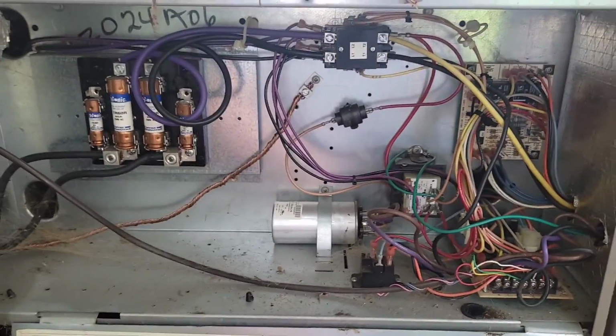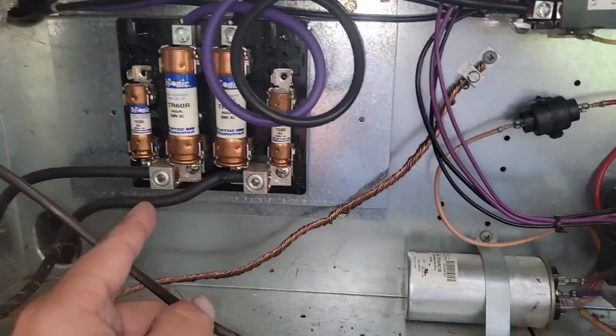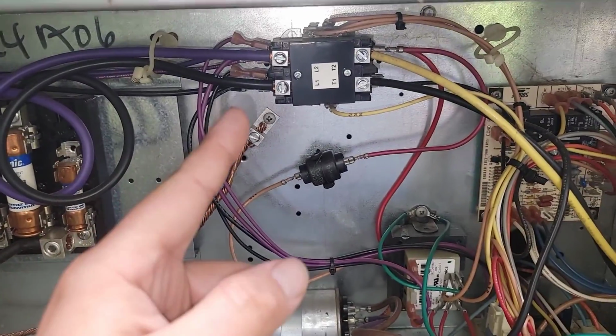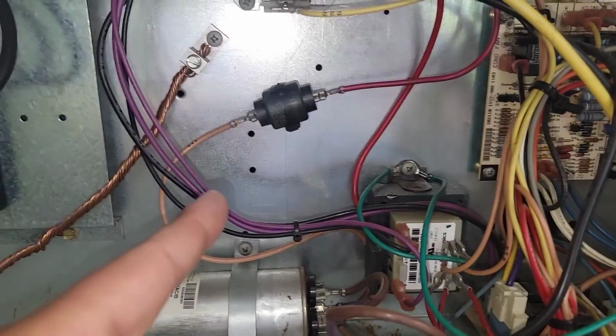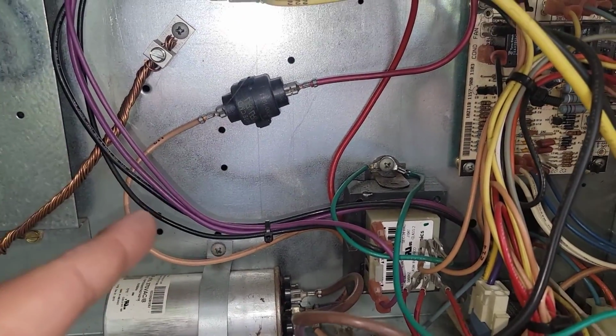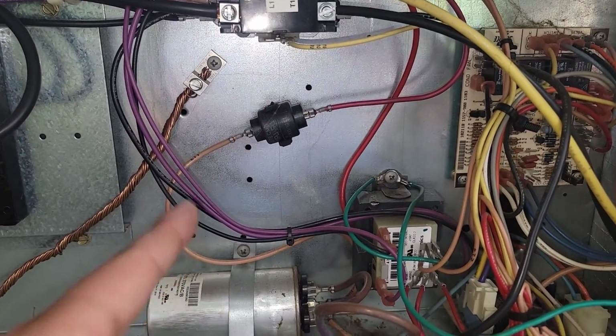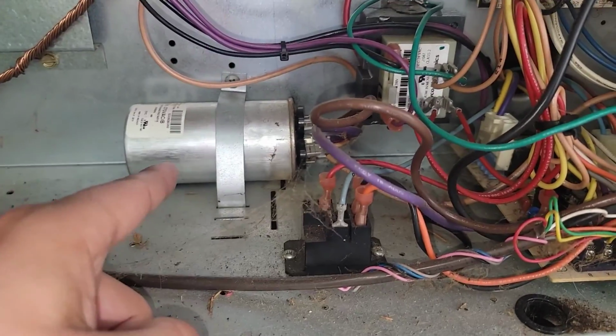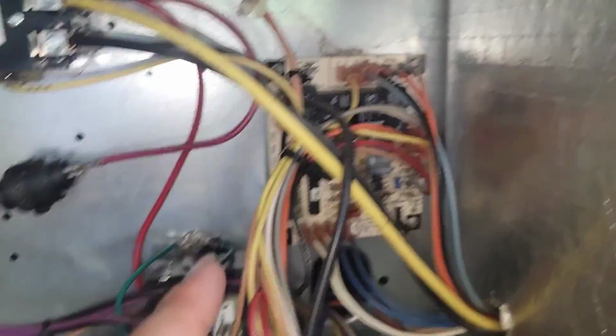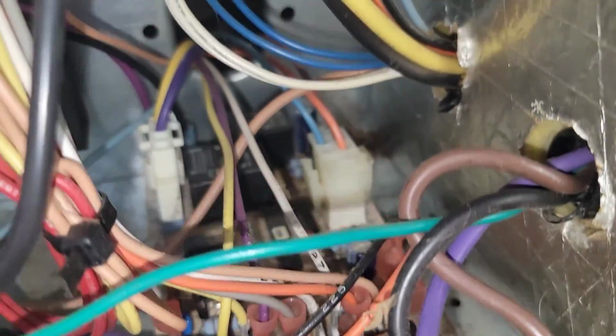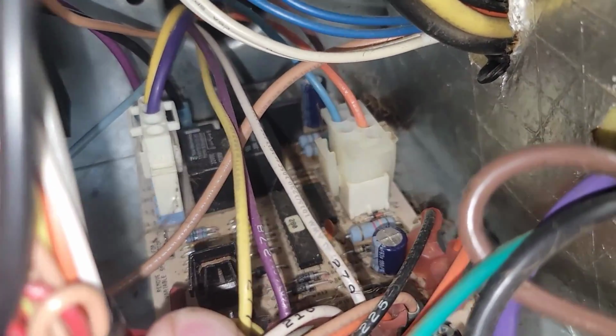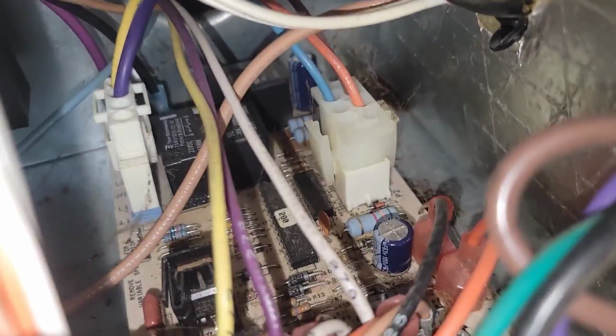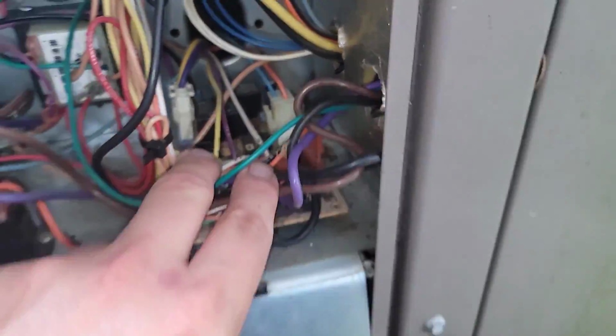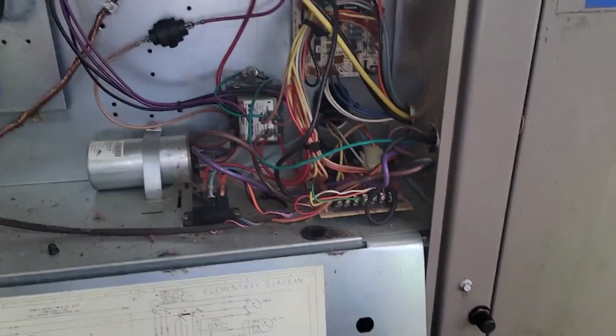This is the electrical components. Here is where the power comes in. Then we've got our contactor. We got a PTC, so that's for starting that compressor and dropping the start winding out. Run capacitor. We got our transformer, defrost control board, and this is our fan heat control board. I've seen these burn up and it doesn't look burnt, but we're going to find out what's going on.